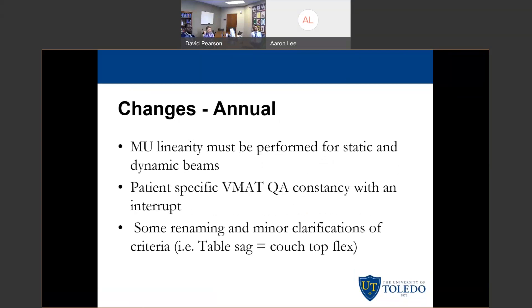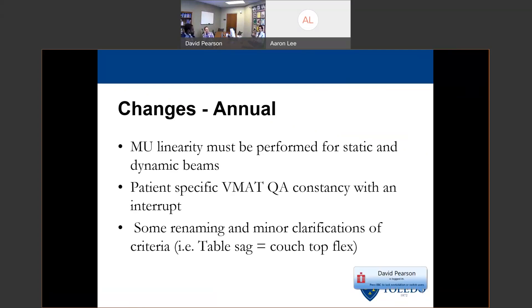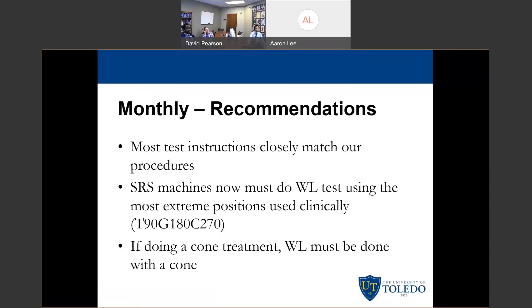For the annual changes, MU linearity must now be performed for both static and dynamic beams, because in many linacs the method of delivery for MUs actually changes when you have a dynamic beam. The recommended way to test this is to have two open fields, with one having the MLC pair furthest away from the central axis moving during delivery. They also said to do a patient-specific VMAT constancy test — the same one as the monthly — but this time introduce a beam interruption midway through and then start it up again to make sure it still matches. There were also a random assortment of renamings and minor clarifications, such as changing the name of the table sag test to Couch Top Flex.